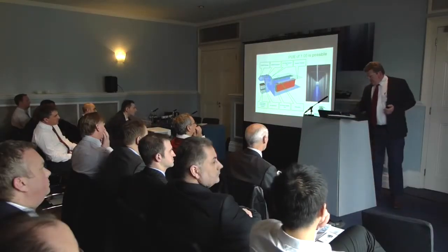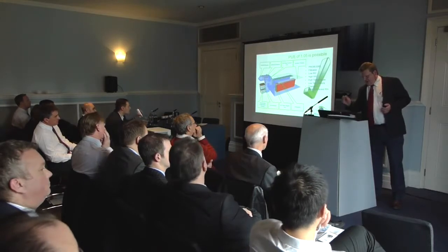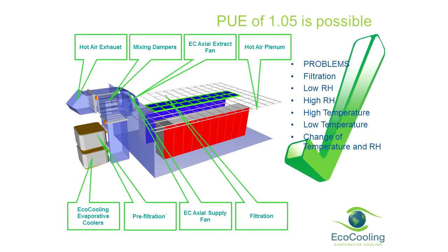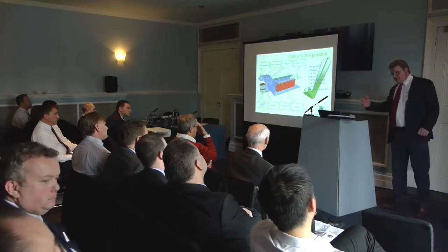So, with that system, I put a big tick there. That's a bit of a sales big tick, because with a fresh air system and slightly changing humidity, it isn't an absolute. But you can go a long, long way to solving those problems. And now we personally have got over 300 data centres running using fresh air evap cooling in the UK and across Europe without seeing significant changes in reliability beyond normal failure rates anyway.